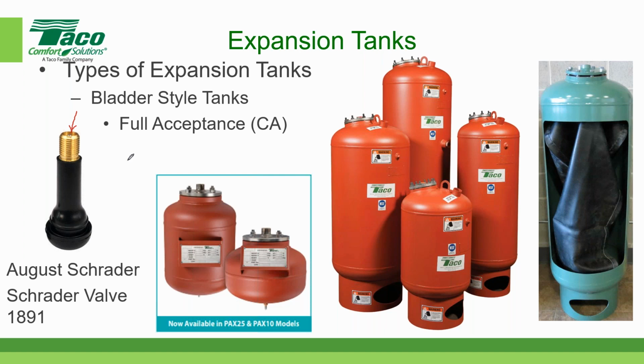There's a couple of questions here, Rich. Explain how having more than one expansion tank at two different locations works with a system. We do not recommend that you have expansion tanks at two different locations. You pick one location, and hopefully you've selected the location that is on the suction side of the pump, which is known as the point of no pressure change.